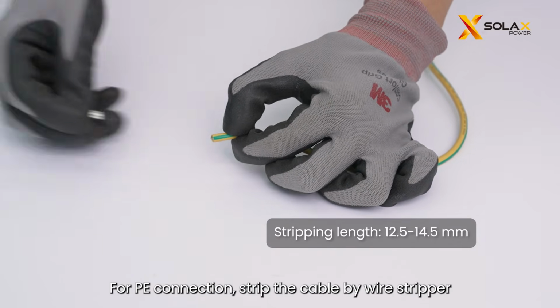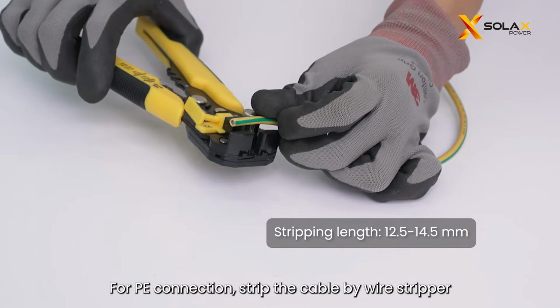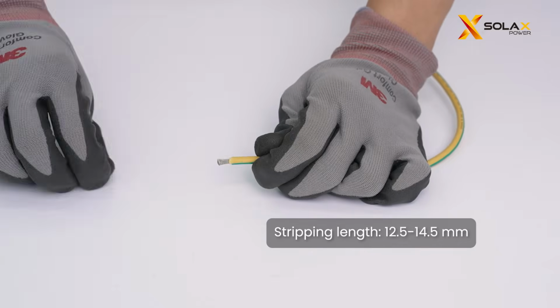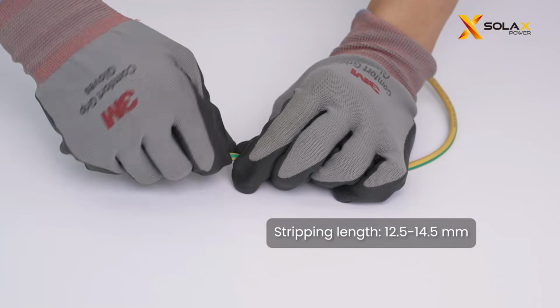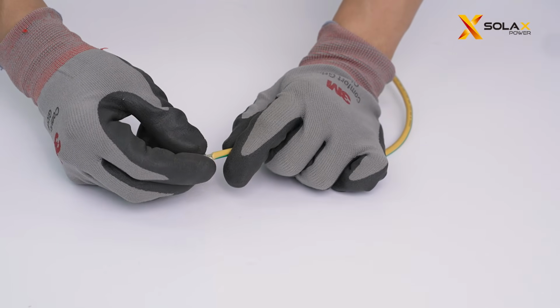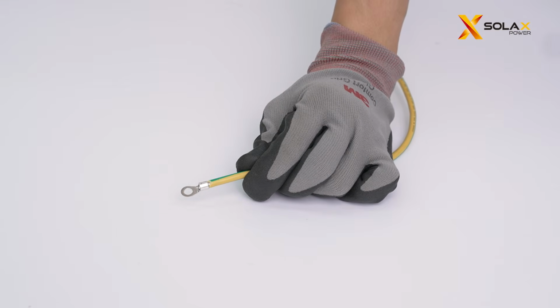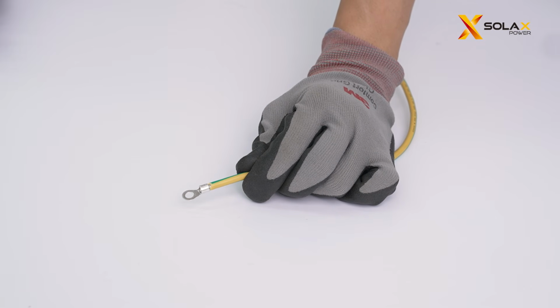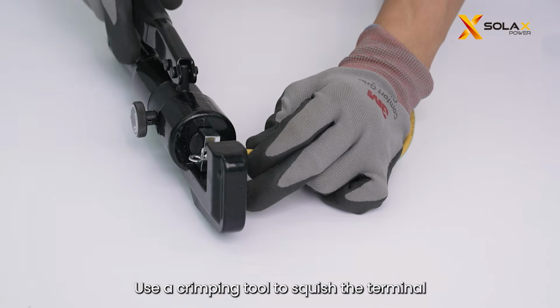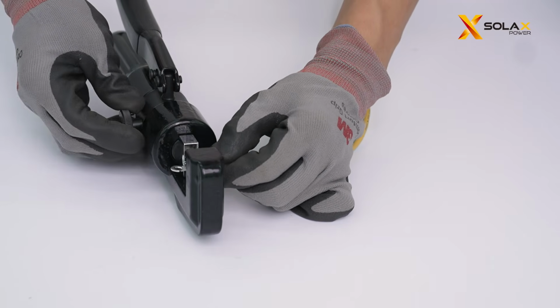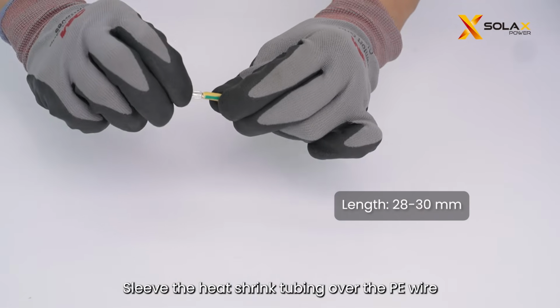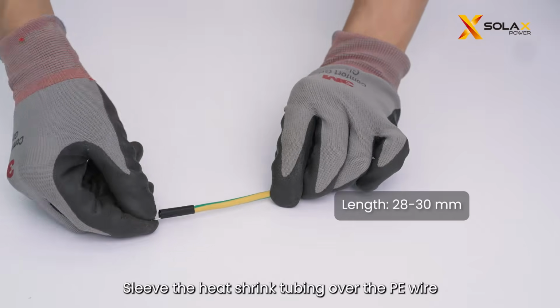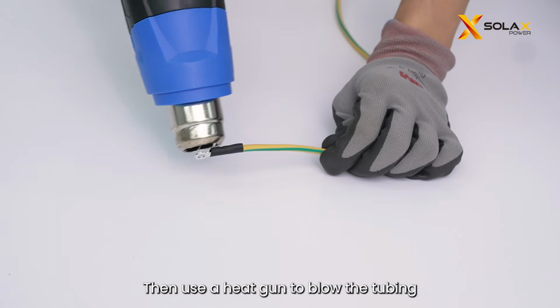For PE connection, strip the cable by wire stripper. Use a crimping tool to squish the terminal. Sleeve the heat shrink tubing over the PE wire. Then use a heat gun to blow the tubing.